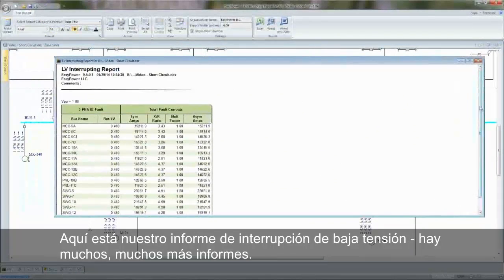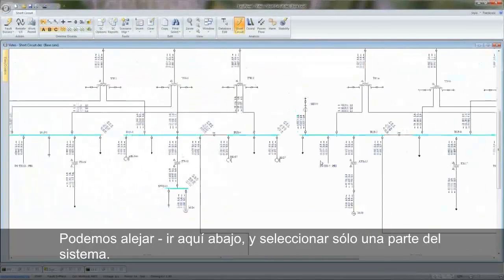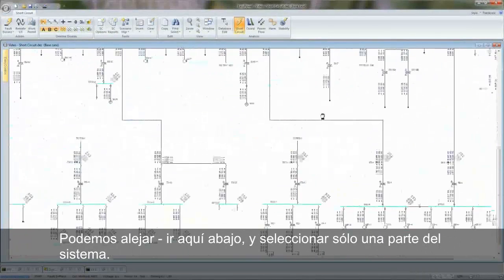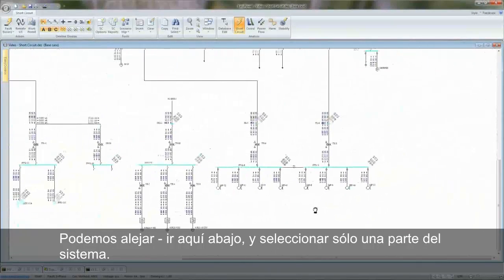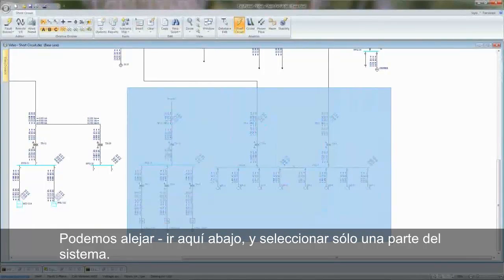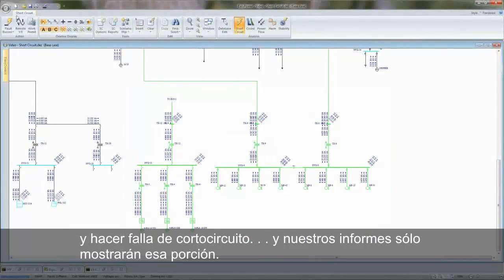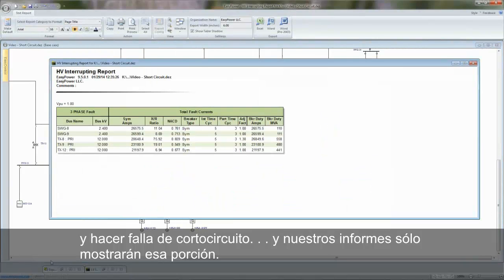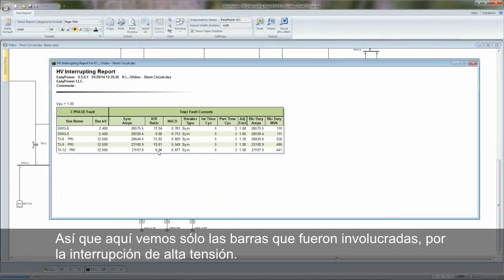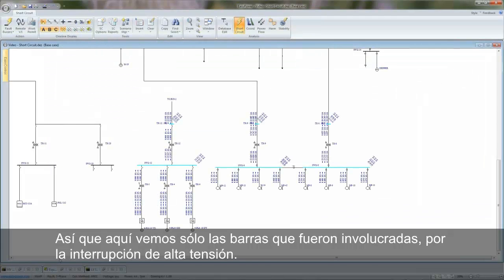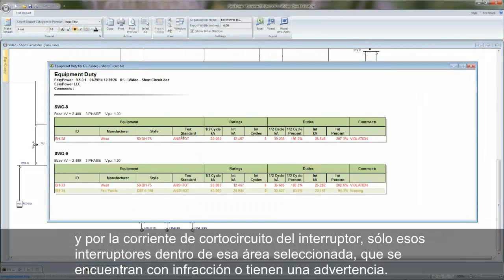There's many, many more reports. We can zoom out, go down here and select only a portion of the system and fault, and our reports will only show that portion. So here we see only the buses that were involved for the high voltage interrupting report. And for the breaker duty, only those breakers within that selected area that are in violation or have a warning.